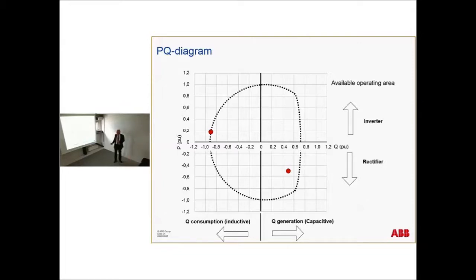So at the same time, we are sending active power, we can absorb or generate reactive power within this area here. So it works like a motor or a generator, but the reaction time is in milliseconds compared to a generator, which has a reaction time of seconds.